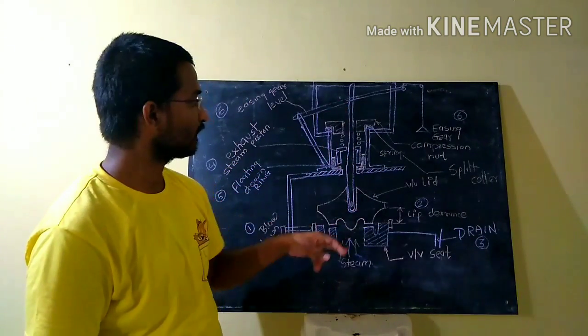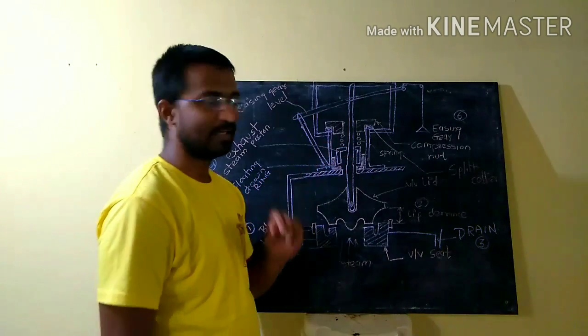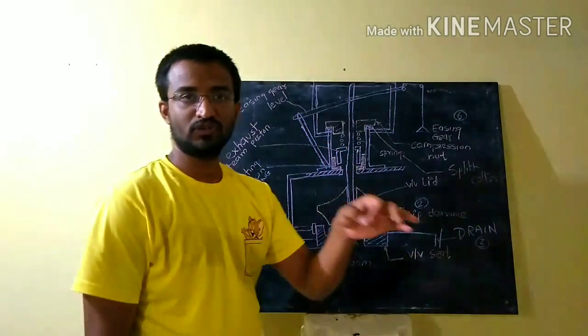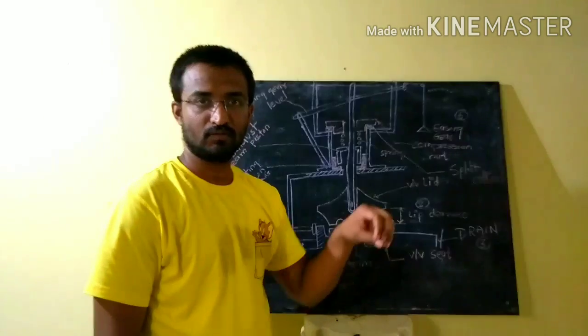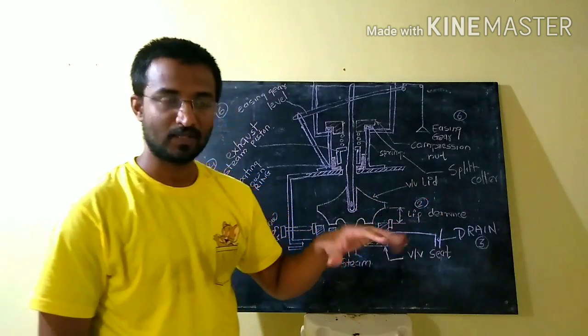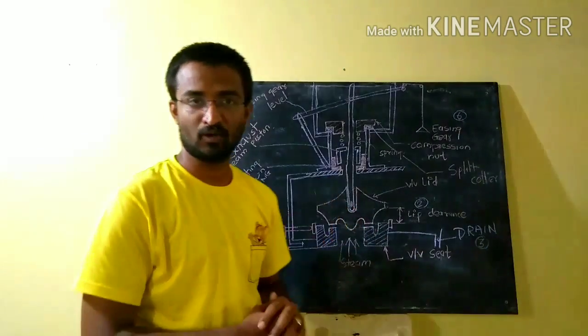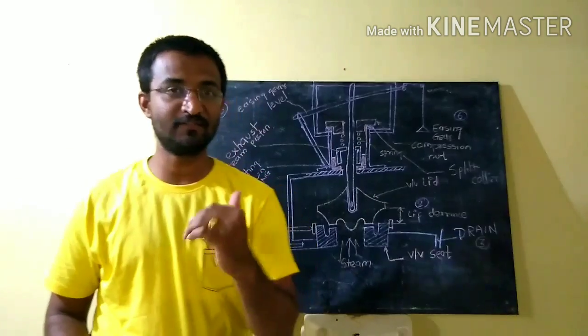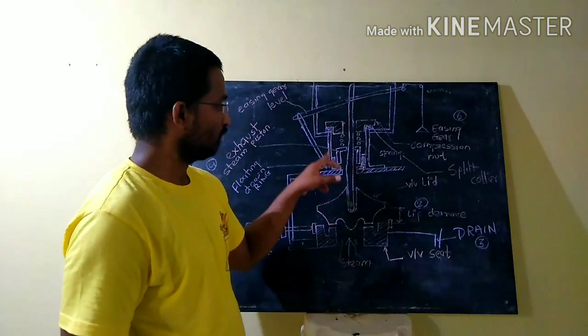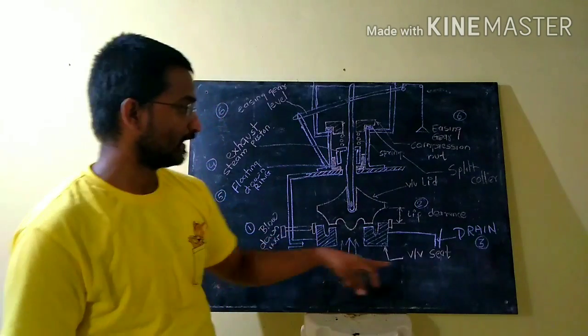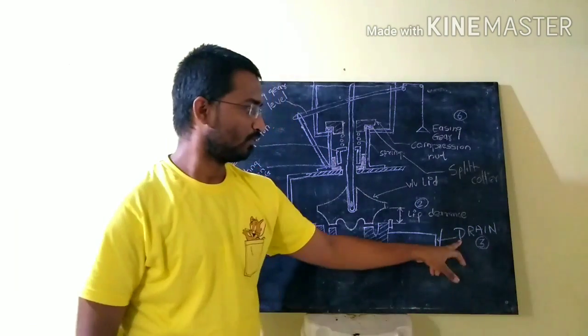If it is fine, then come to the spring. For the spring, you just do the drop test. From a certain height, you just throw the spring and check whether it is bouncing back or not. So you will find out whether the stiffness has remained or not. After the spring, once you assemble all the things, important is the drain. Very important.